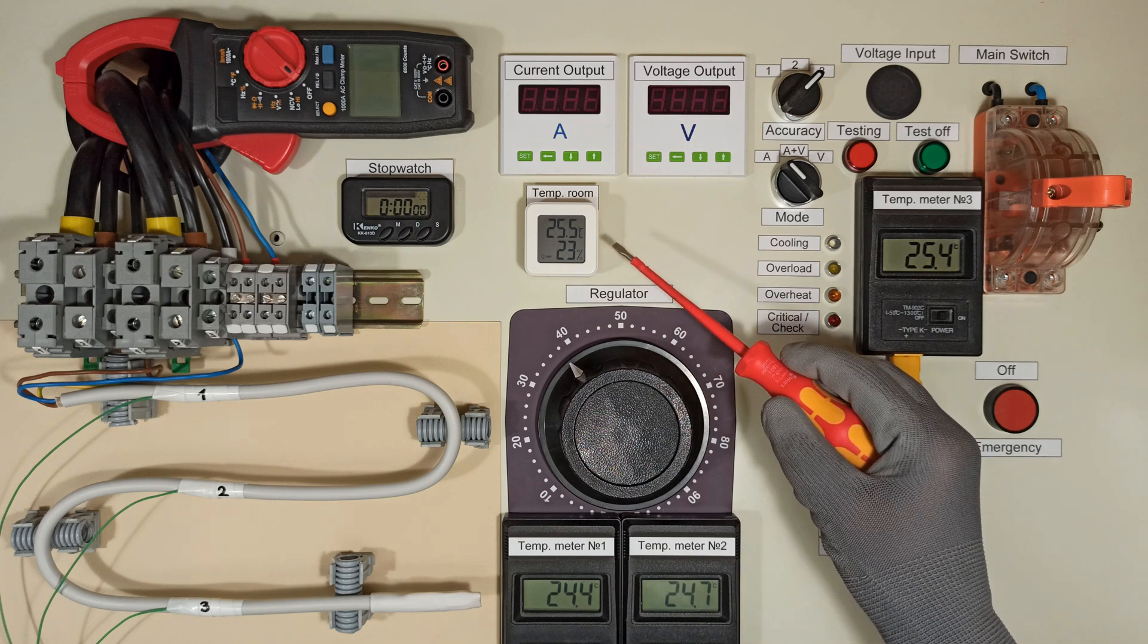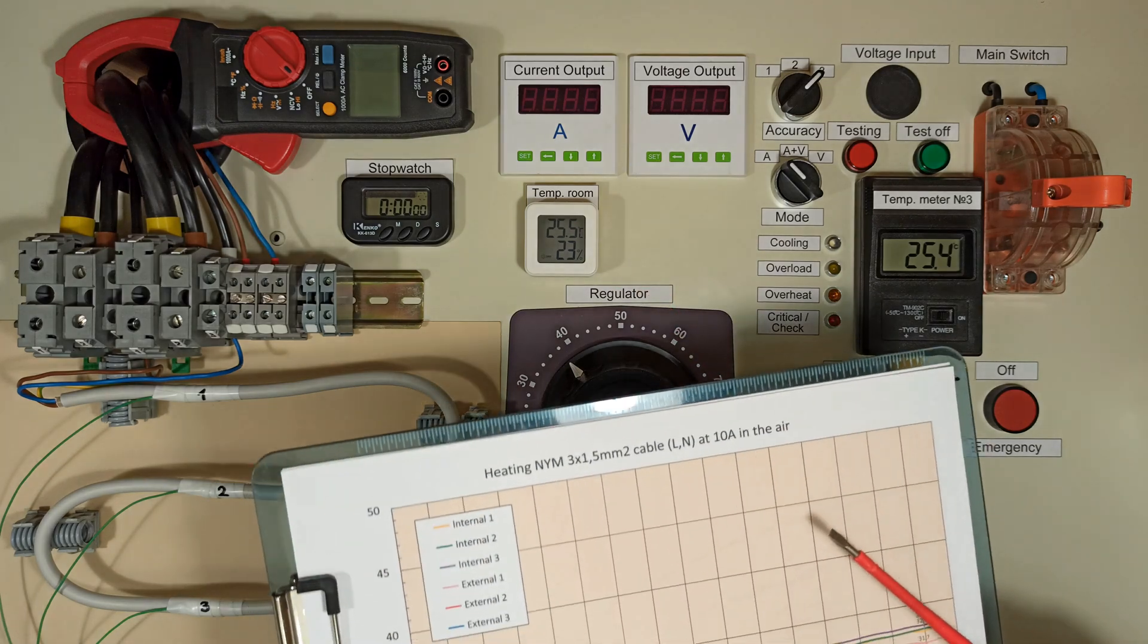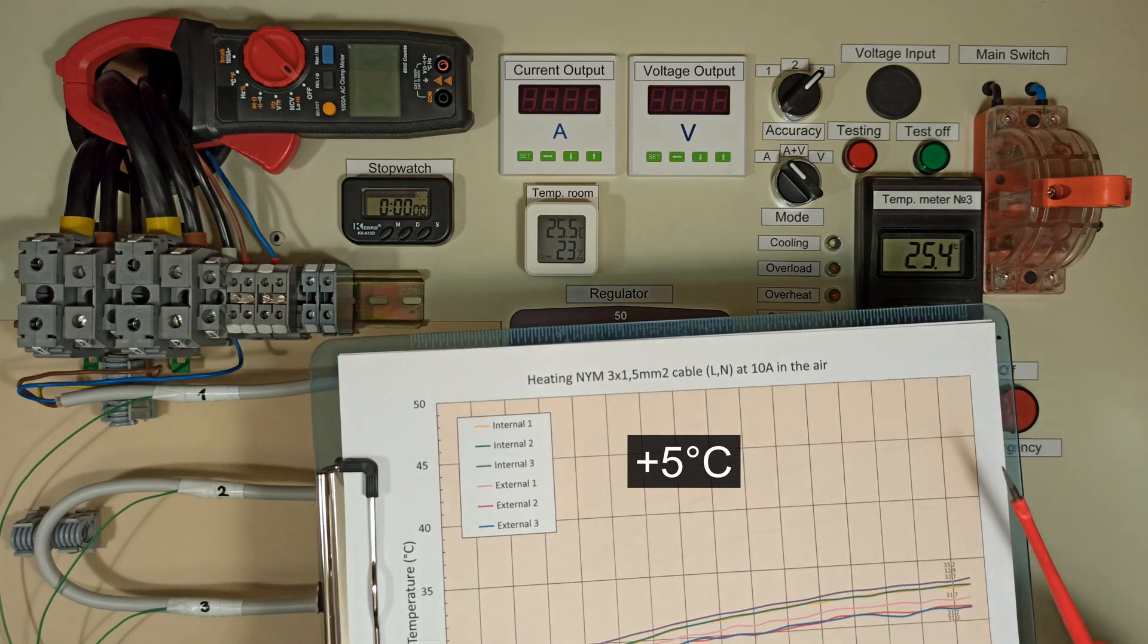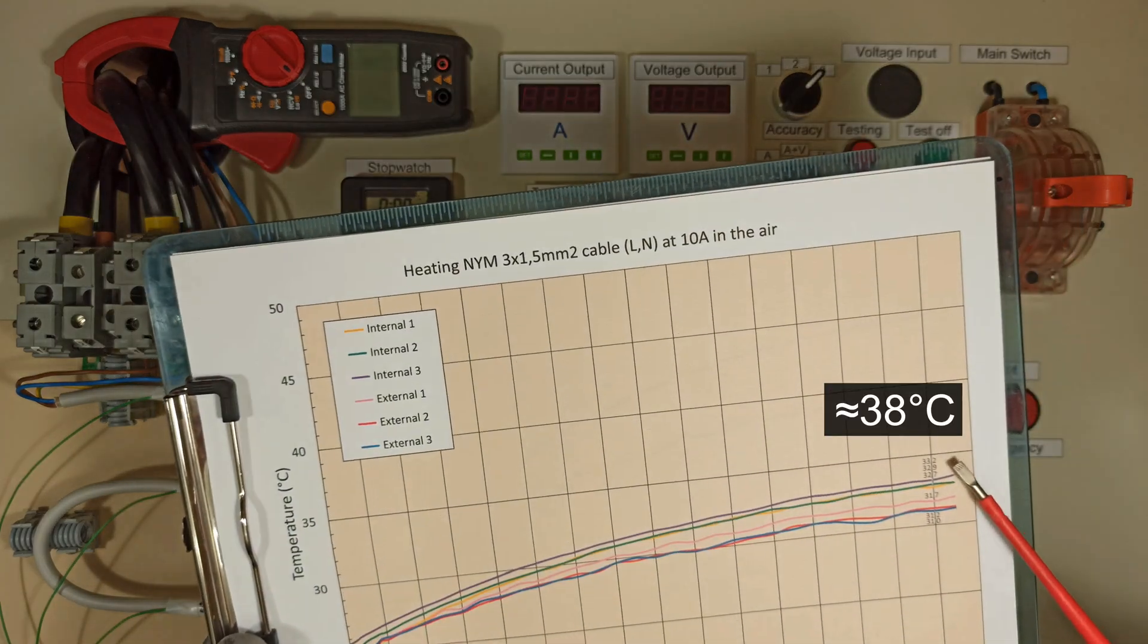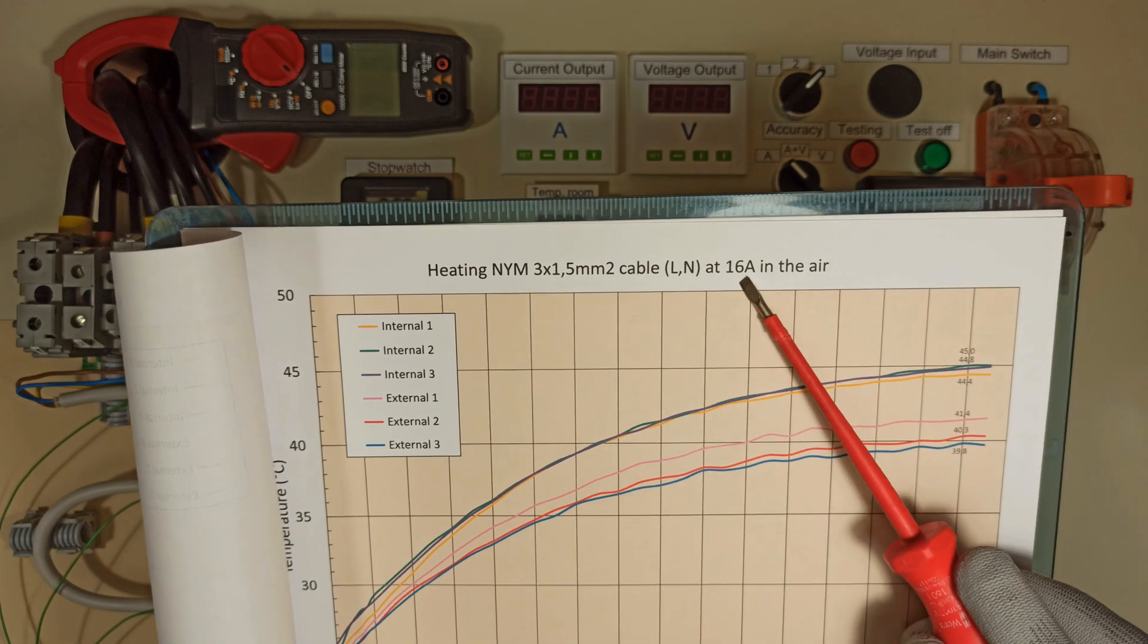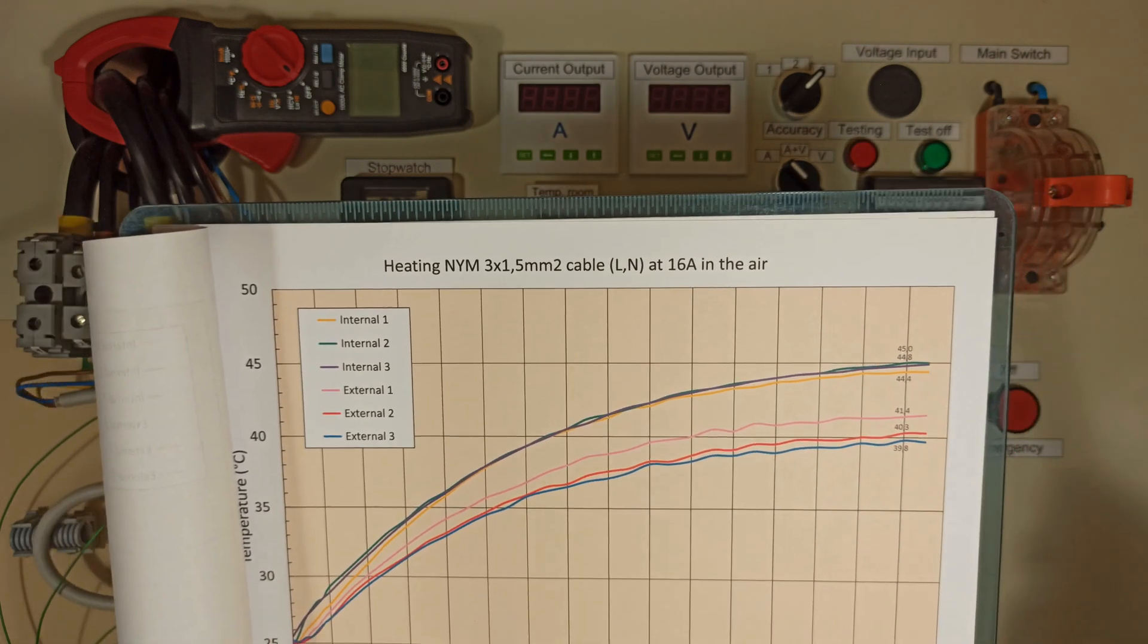Note that the room temperature is around 25 degrees. At 30 degrees, I think the temperatures would be about 5 degrees higher. So, at 10 amps, it would be 38 degrees, and at 16 amps, it would be around 50 degrees. A good result.